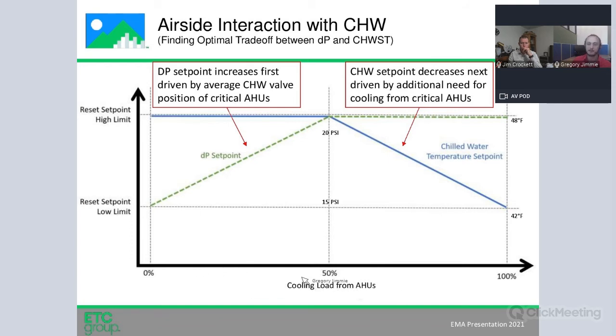As the first half of that loop gets to 50%, where 100% is basically your design point, 50% would be somewhere halfway between that. So you drive your differential pressure up from minimum to maximum. I've shown here maybe going from 15 psi to a 20 psi differential pressure. And then once you get to your maximum pressure, you're going to start stepping down your chilled water temperature as the cooling demand continues to go up.